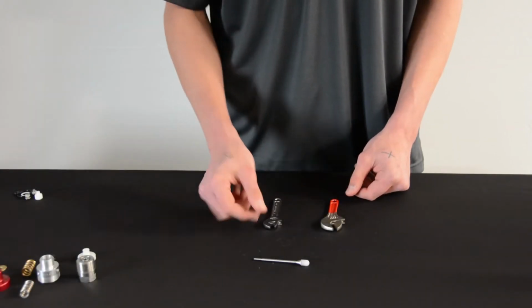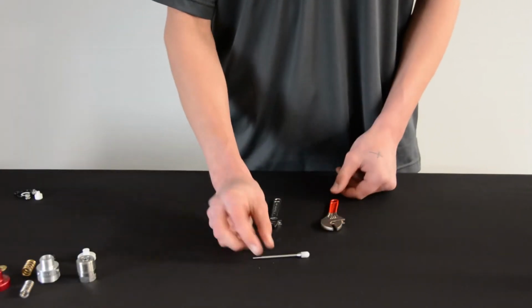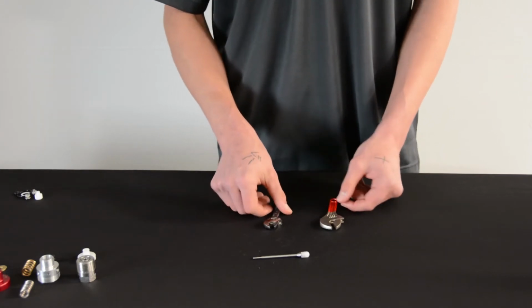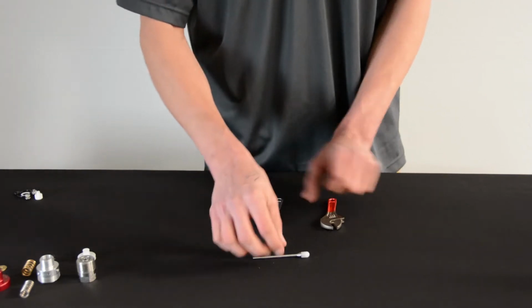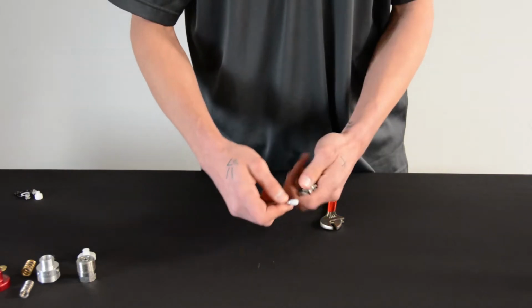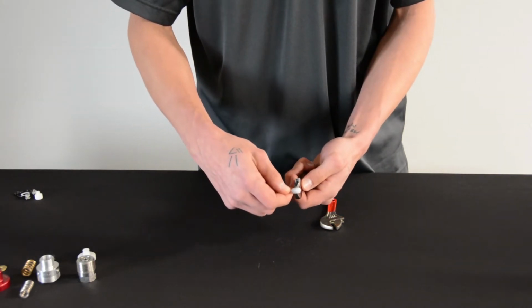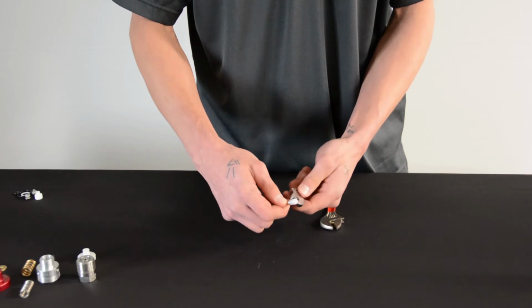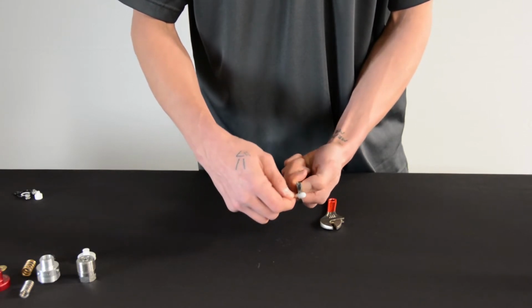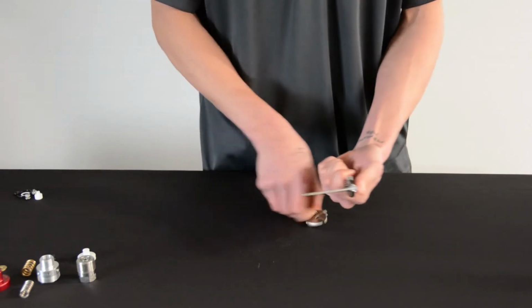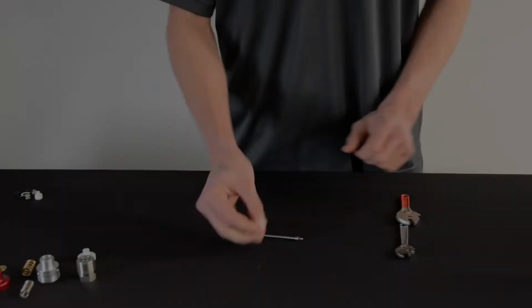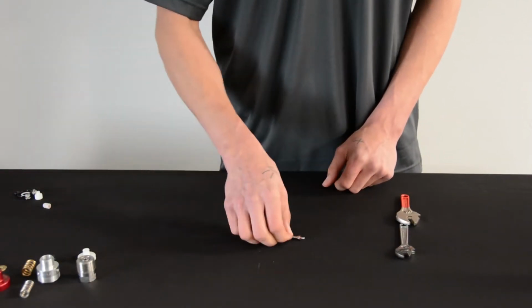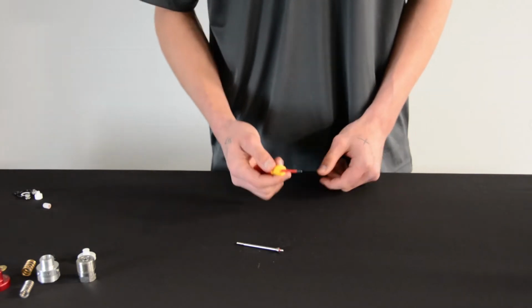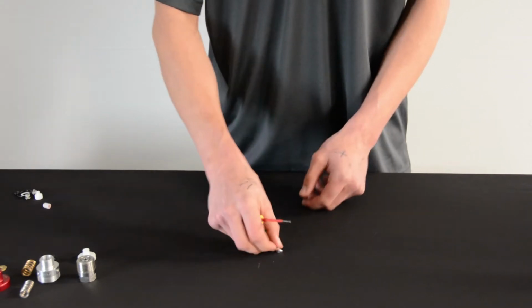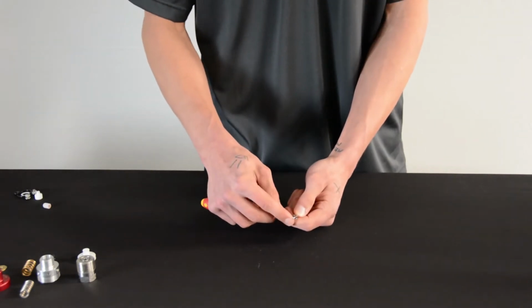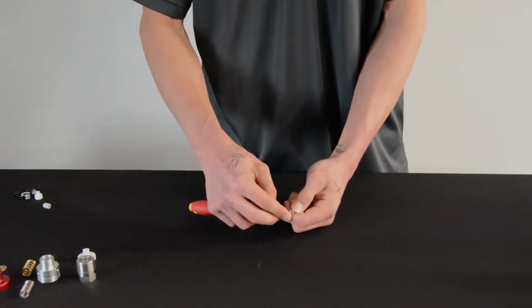Next, we are going to remove the plunger end from our shaft. Using 2 9/32 wrenches or 2 small adjustable wrenches, remove the plunger end from the shaft. You can discard the plunger end, but you want to keep the shaft. It might be a good idea to take a small screwdriver and abrasive brush and clean off some of the excess Loctite from the threads on the piston shaft.